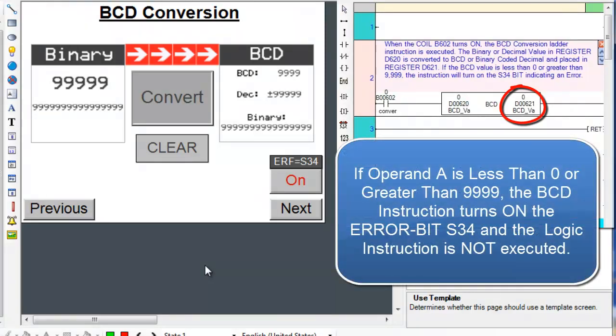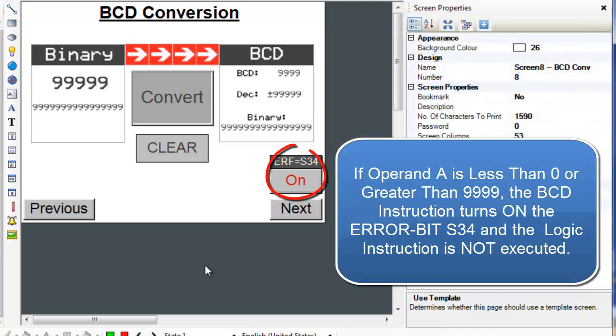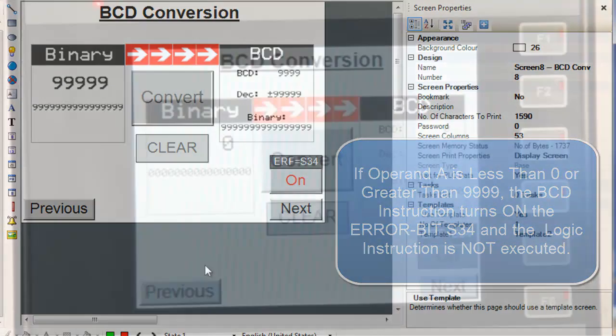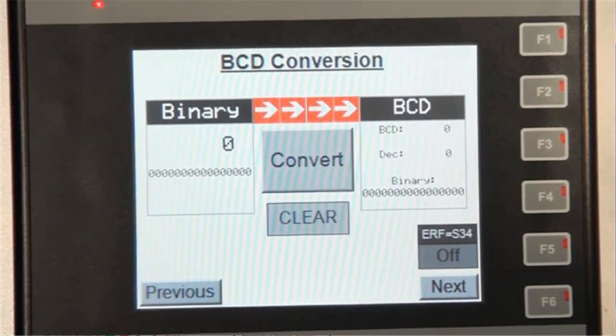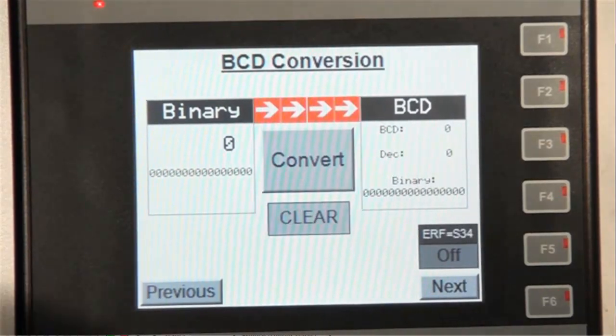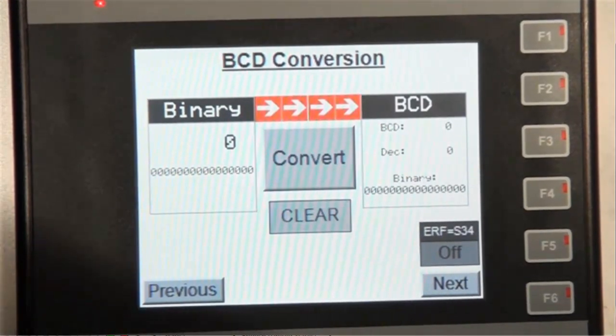If Operand A's value is not in the range of 0 to 9999, the conversion is not executed. The instruction turns on an error flag, which is the bit S34. Now let's examine this ladder instruction on the HMC.